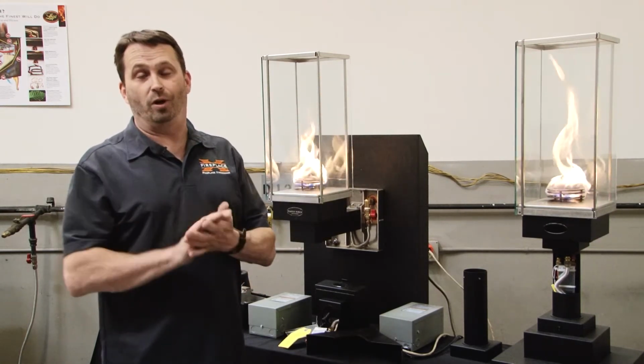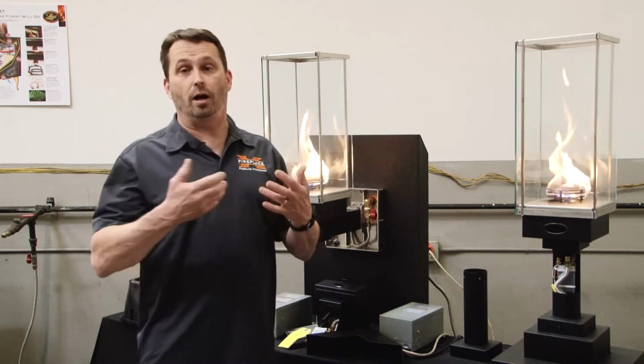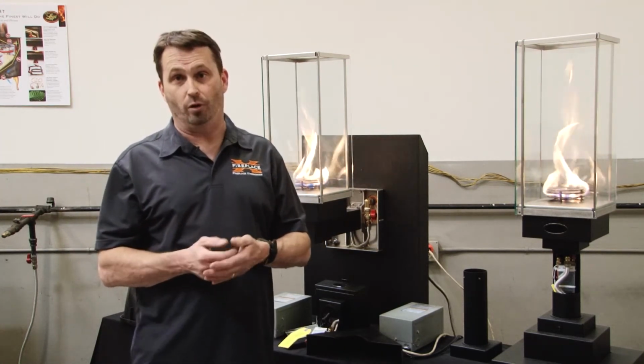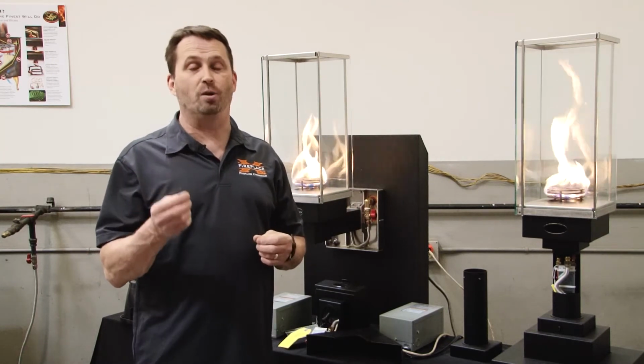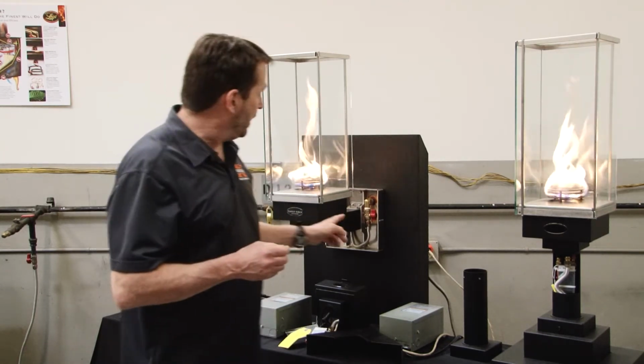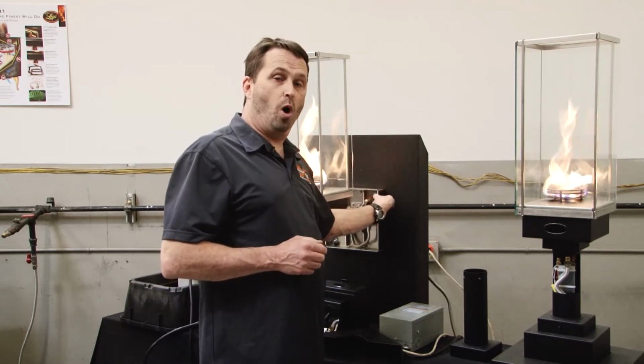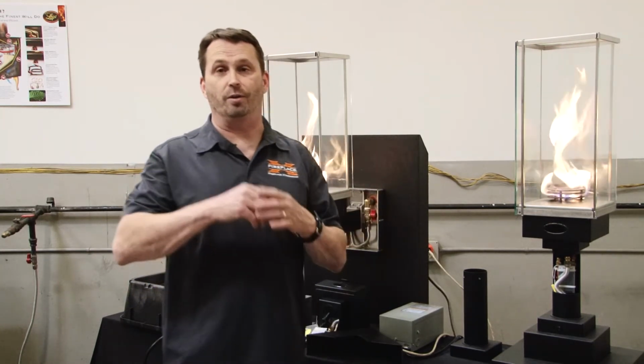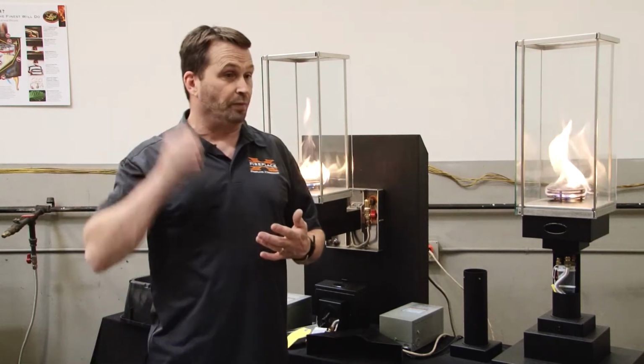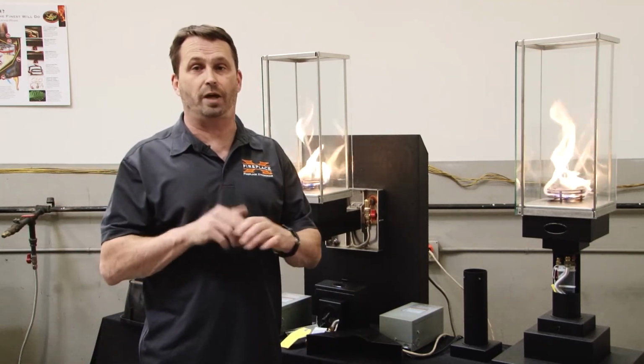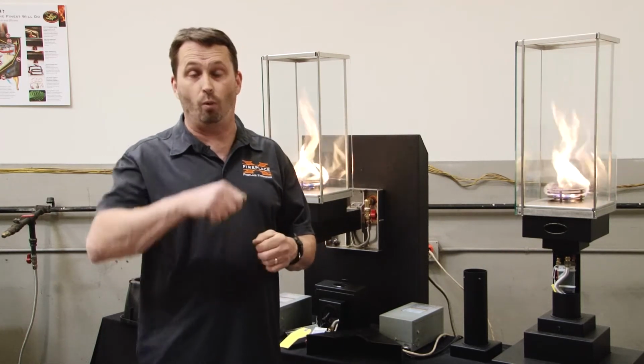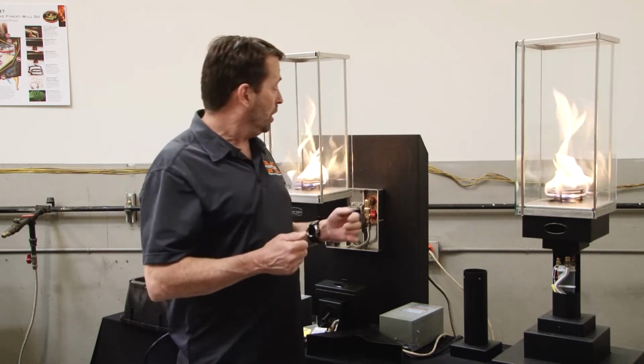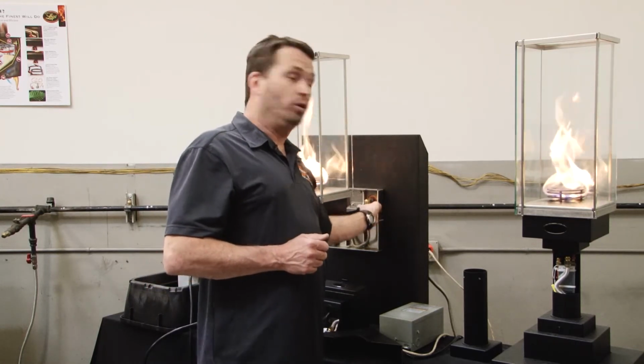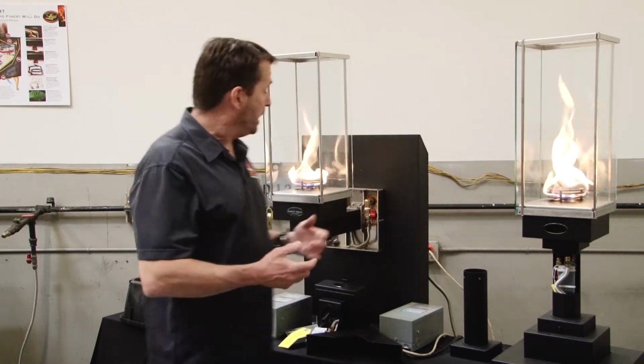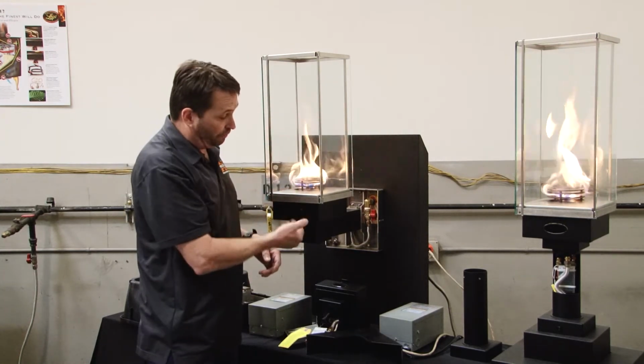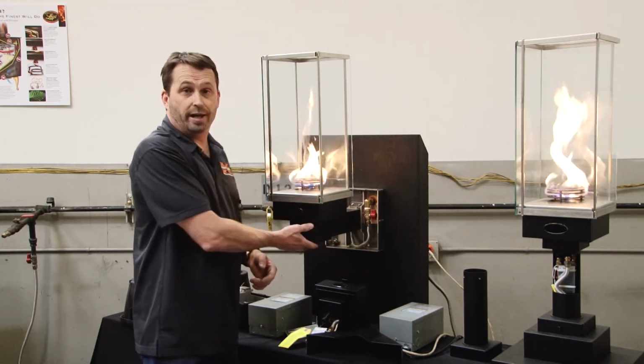You'll probably notice, if you read the manuals, that we made the warnings on negative pressure much clearer. It's really critical on any commercial or residential building that any penetration from the wall mount to the inside of the building is completely sealed, and not just stuffed with some K-wool or fiberglass insulation. We want it silicone, we want it completely sealed. If the negative pressure is strong enough within the building, it can pull not only the heat but also the flames down into the base of the head assembly.